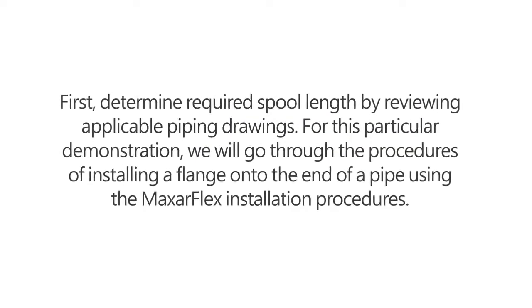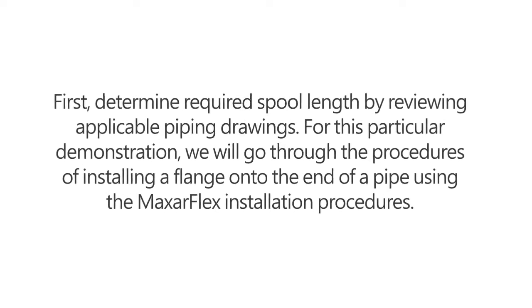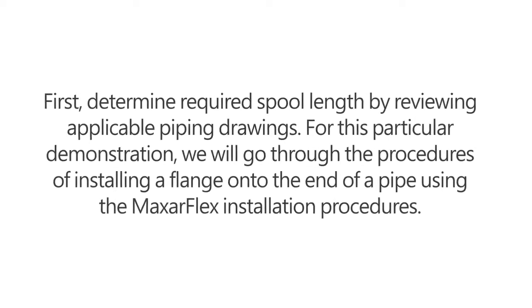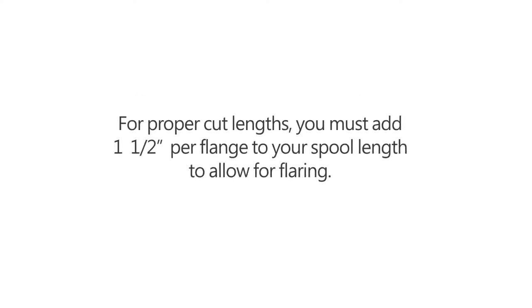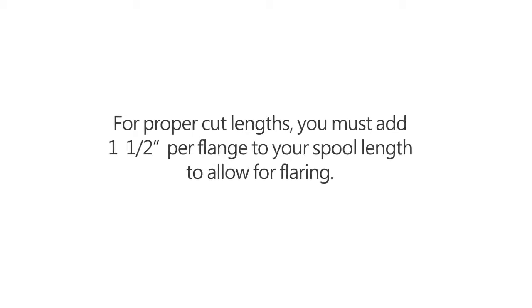First, determine required spool length by reviewing applicable piping drawings. For this particular demonstration, we will go through the procedures of installing a flange onto the end of a pipe using the MaxarFlex installation procedures. For proper cut lengths, you must add one and one half inch per flange to your spool length to allow for flaring.